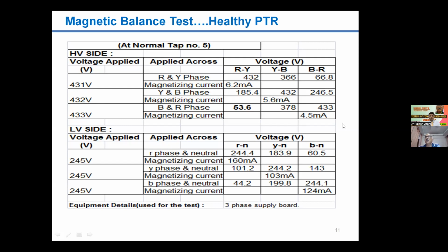But if there is some problem in any transformer, as I discussed, different issues may be there, sometimes even a fault. Accordingly, the result will give you some insight that some problem has taken place inside the transformer. You cannot say from one test that this kind of issue is with the transformer. Many times you do many tests to draw inferences about what kind of problem has taken place with the transformer during its operation. Sometimes the problem inside the transformer may even be because of a fault in the outside feeder, depending upon the conditions.